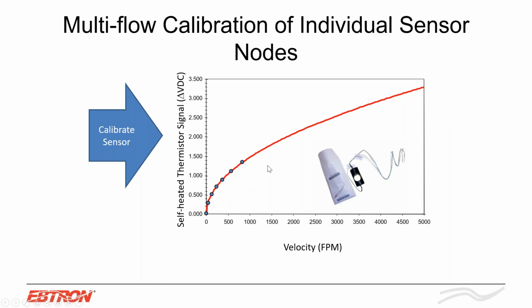One thing again to remember is we use bead-in-glass thermistors. We're the only manufacturer that does bead-in-glass. And we calibrate these at multiple flow rates. So for our duct mounted, it's 16 points from 0 to 5,000 feet per minute. And what you'll see is that even at low flows, we still have a high signal resolution. So that makes thermal really good at reading in outside air intakes because of the sensor signal resolution right here.